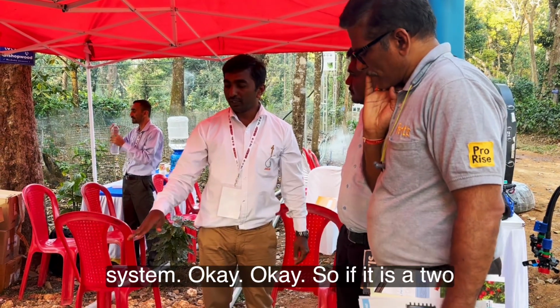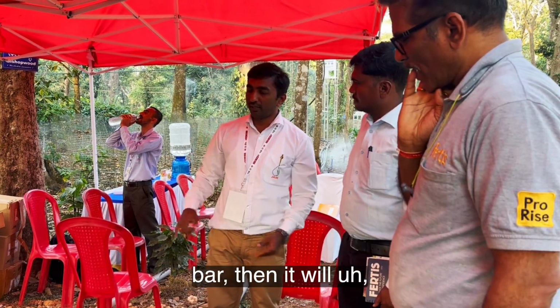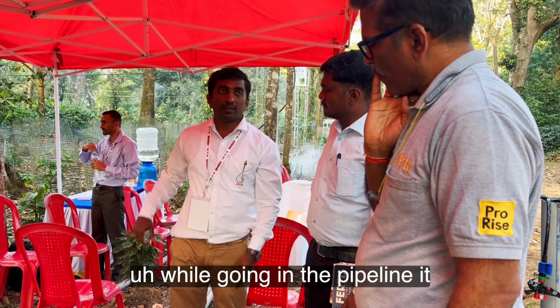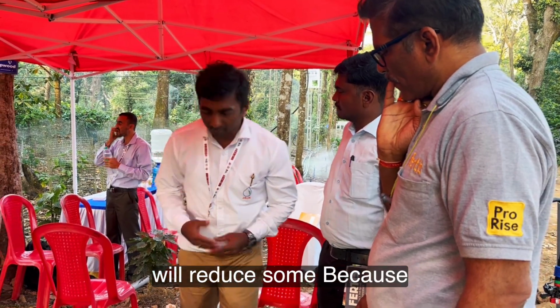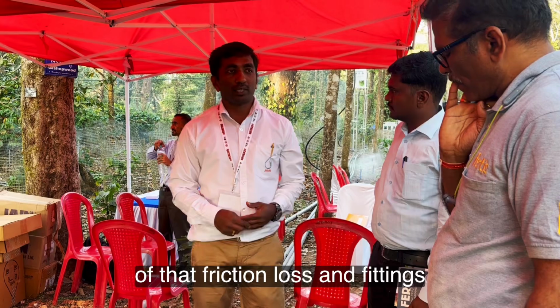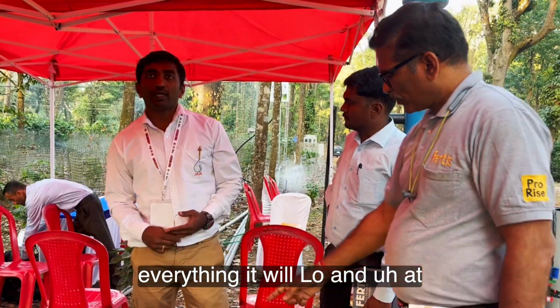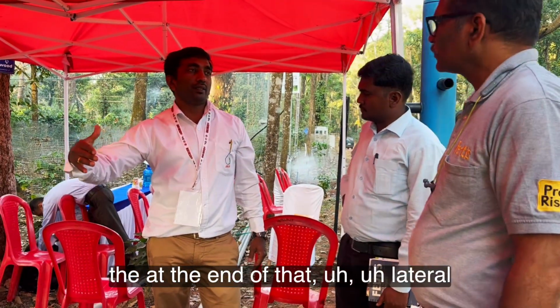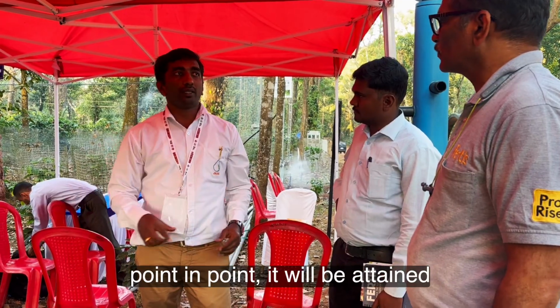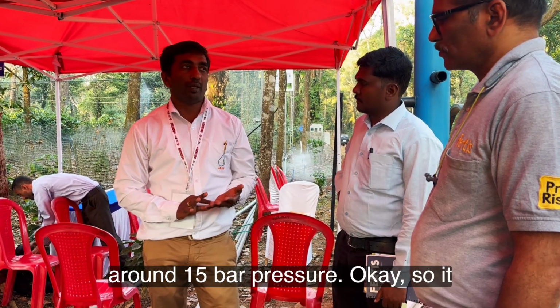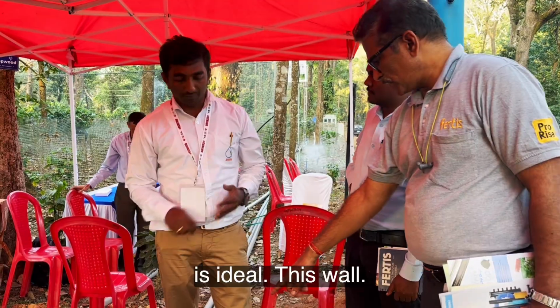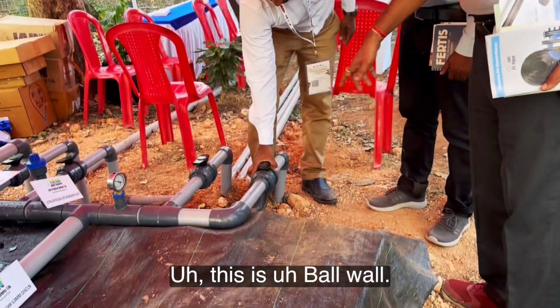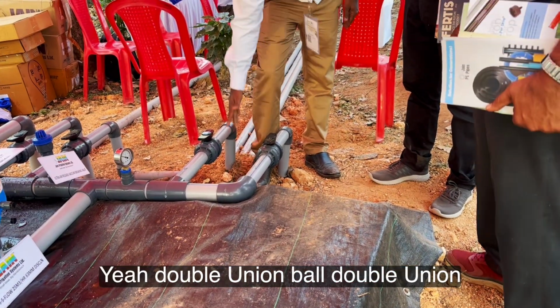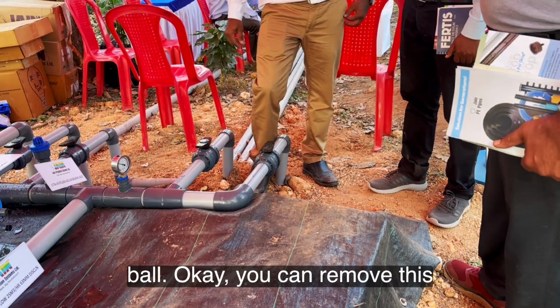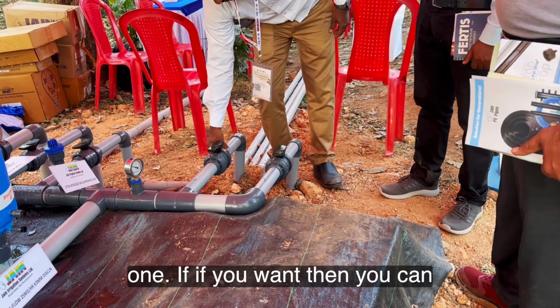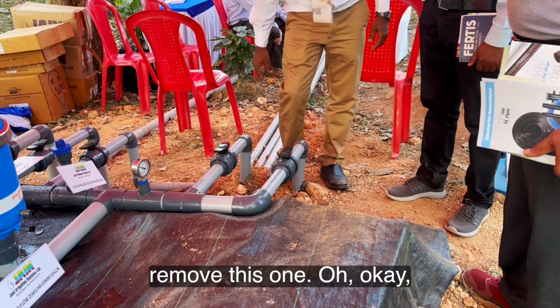If it is 2 bar, then while going through the pipeline it will reduce because of friction loss and fittings, everything. At the end, at the lateral inlet point, it will be around 1.5 bar pressure. So it is the ideal pressure. This valve is a ball valve, a double union ball valve. You can remove this one if you want.